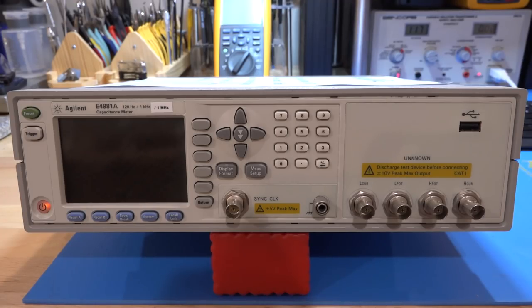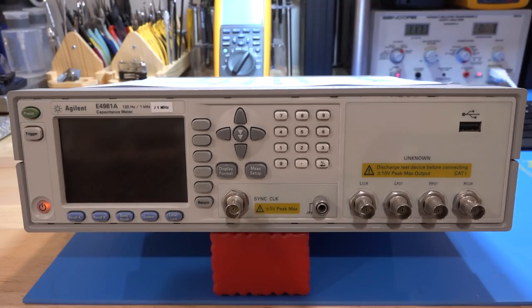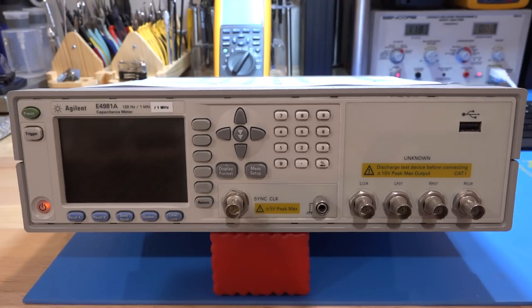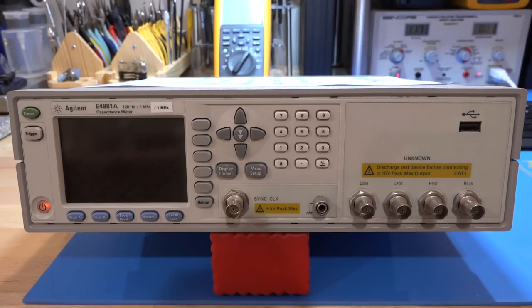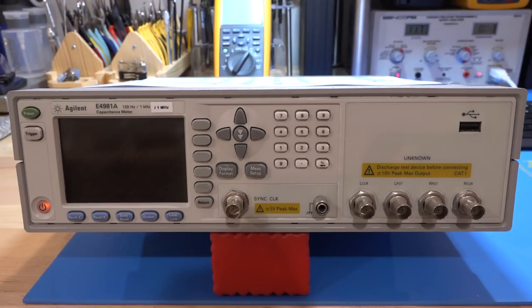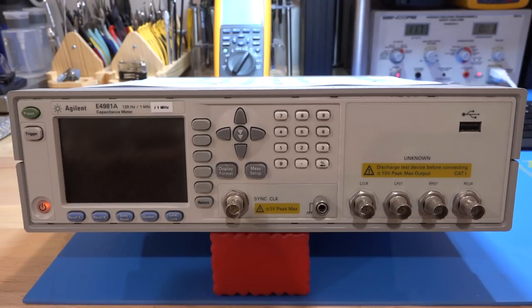Well, this particular unit is intended for very fast measurements and this is essentially for production line measurement. Not only can it measure capacitance at 2.3 milliseconds if you're running it at 1 megahertz, it also has exceptionally good accuracy. This is a 0.07% accurate capacitance meter. So it's really intended for characterizing and binning very precisely ceramic capacitors in a production environment.